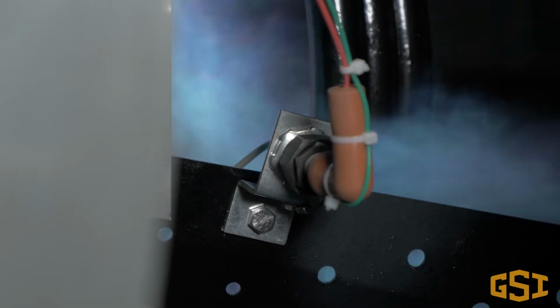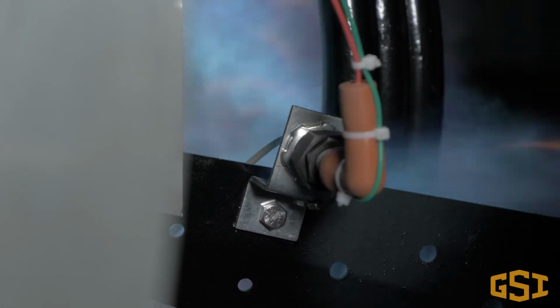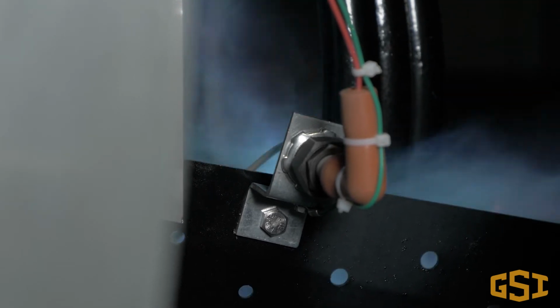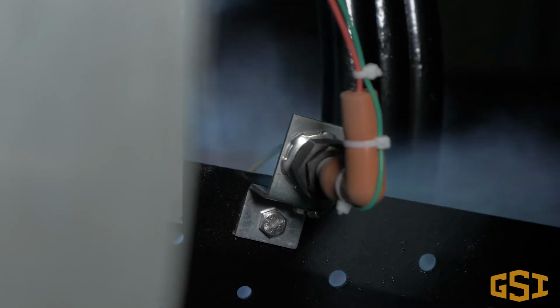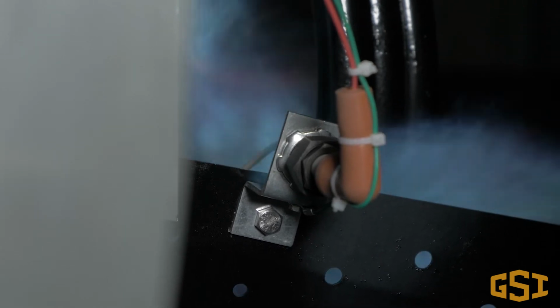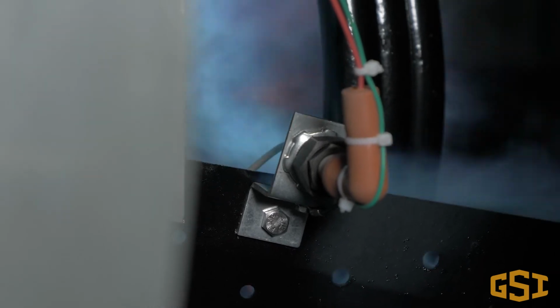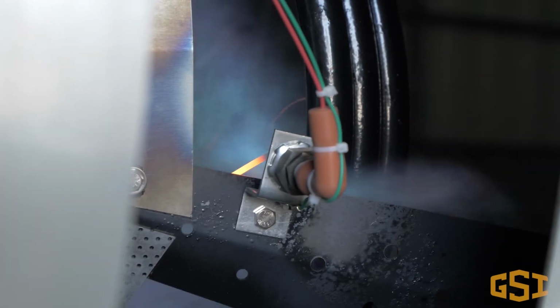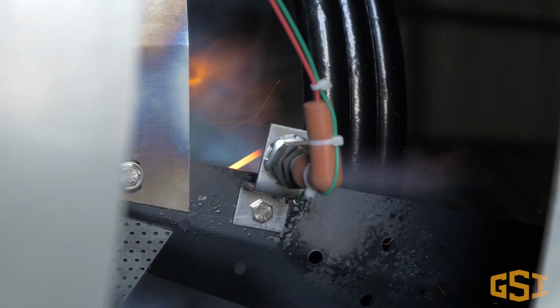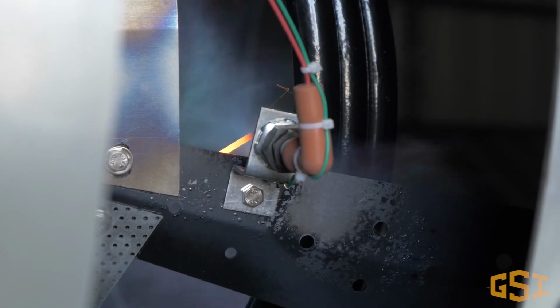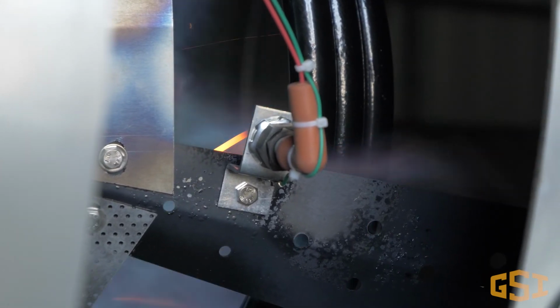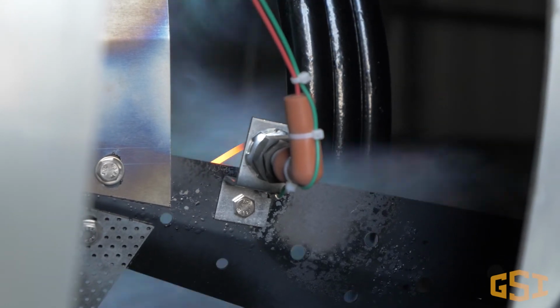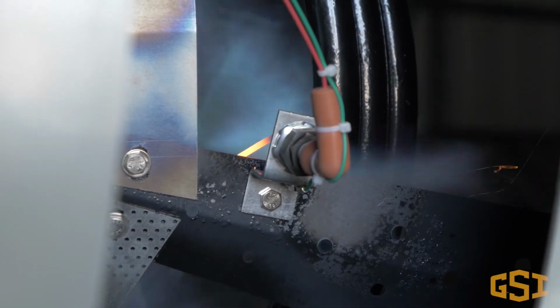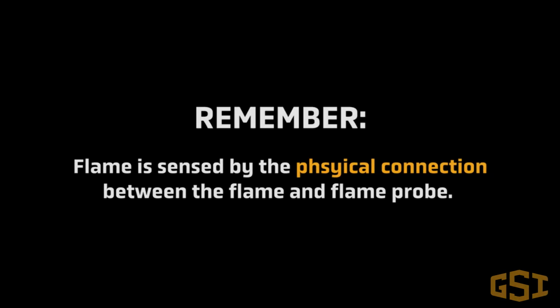Because the flame and flame rod are part of the electrical circuit, the physical connection between them must always remain in place. Flame sensing is a physical connection when the flame is in contact with the flame rod. Loss of flame is an open circuit, like turning off a light switch in your home. Now is a good time to point out the common misconception that a red-hot flame rod is sensing flame. A flame probe can be red hot, but still not have physical contact with the flame, so you should not associate flame sensing with a flame probe that is red hot. Remember, flame is sensed by the physical connection between the flame and flame probe.